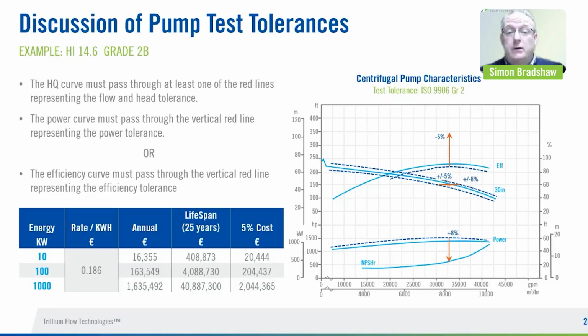This tolerance standard also allows the efficiency to be up to 5% below what the characteristic of the pump sold was, and that is shown by the red line at the top of the graph that says minus 5%. So the efficiency curve must pass through that vertical red line, representing the efficiency tolerance. And if efficiency was important to you, what that means in practicality is that this pump could test 5% low in efficiency, and for a 1 megawatt pump, with European energy prices, that's about 2 million euros more that pump is going to cost you over its lifespan, which is quite a lot, and most likely more than you actually paid originally for the pump.